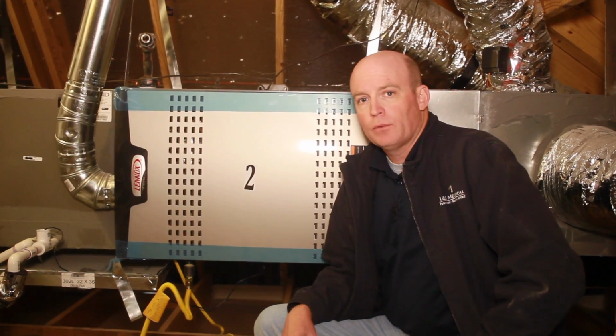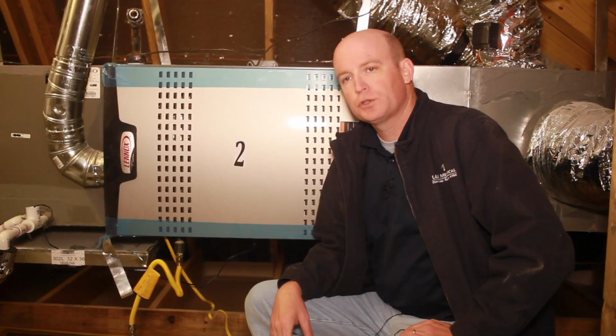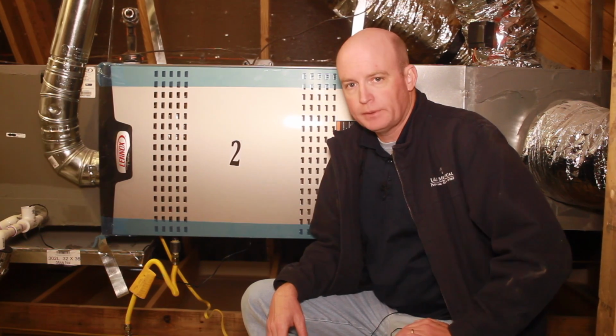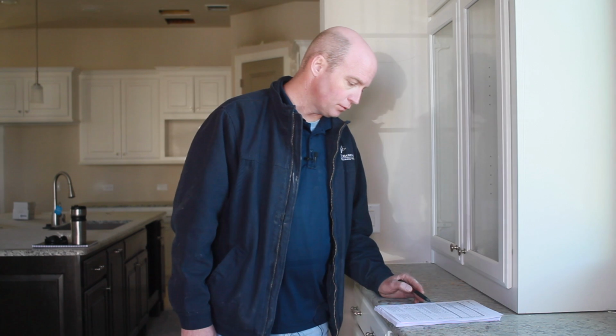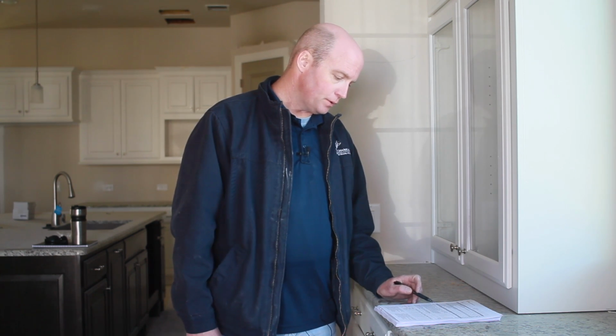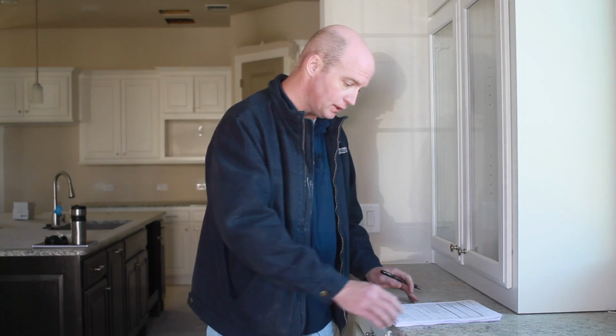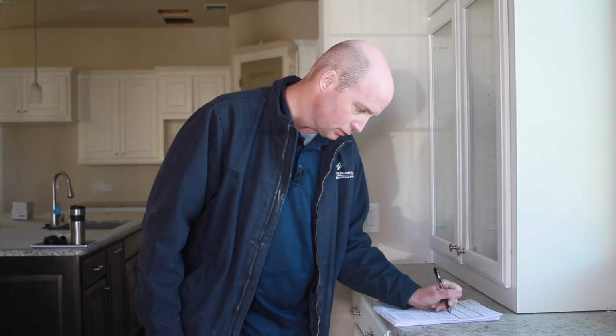The next thing we'll look at will be the paperwork. We'll show you how to fill out the form. Many of you will be doing this online on the iPads. What we're going to do now is fill out the paperwork portion for the airflow test. So we'll be concerned with all of the items 3.1 through 3.8 in the Energy Star design report form. This is on our LNS punch sheet, and we'll fill it out. Now, item 3.1, it asks you, what mode did you test it in? Well, in Texas, we're only going to test in the cooling mode. We're not concerned with the heating mode. So we'll go ahead and mark cooling.